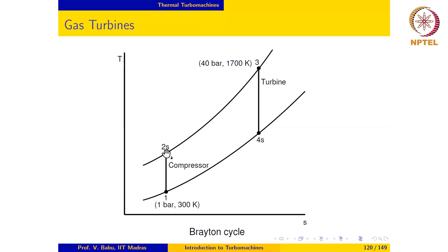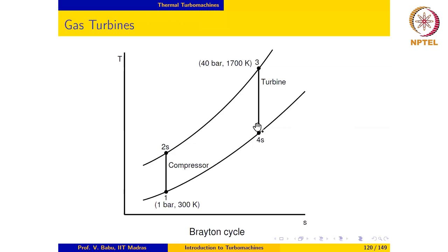Hydrocarbon fuel is mixed with the air and burnt, which increases the temperature of the gases. The high-temperature gases then enter a turbine where they are expanded. The turbine produces sufficient power to run the compressor, and the leftover power is used to run an electric generator in a land-based gas turbine power generation unit. In the case of an aircraft engine, the leftover enthalpy of the gases is converted into kinetic energy in a propulsion nozzle for propulsion.